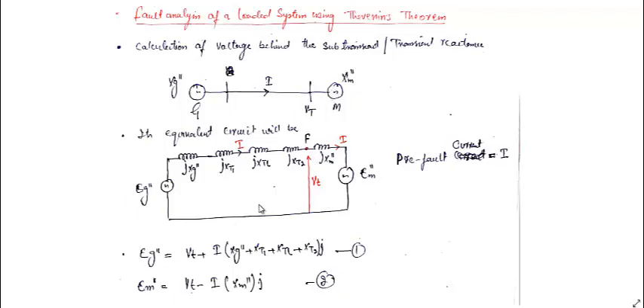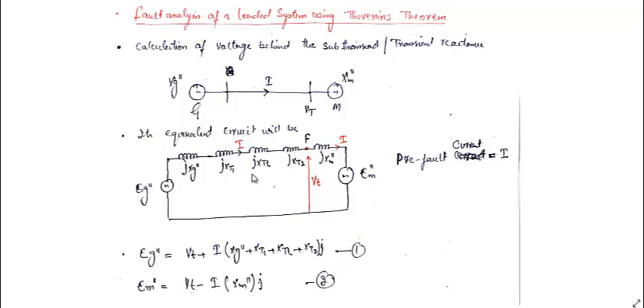Before the fault, this is the current flowing from generator to motor — we call this the pre-fault current. Vt is the pre-fault voltage at the bus to which the motor is connected. Using simple KVL we can relate Eg double dash and Em double dash to Vt. Eg double dash equals Vt plus I times (Xg double dash + XT1 + XTL + XT2), and Em double dash equals Vt minus I times Xm double dash.